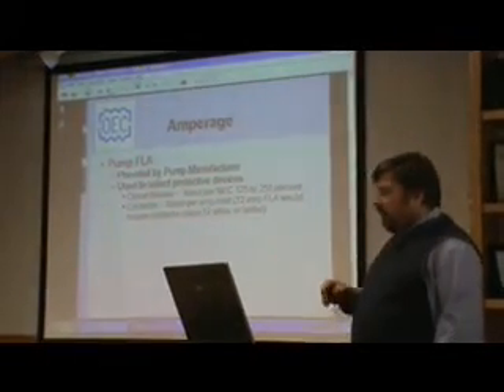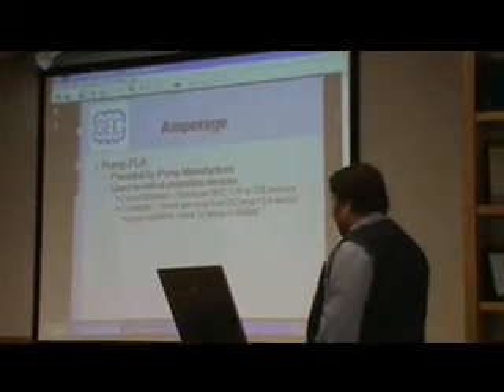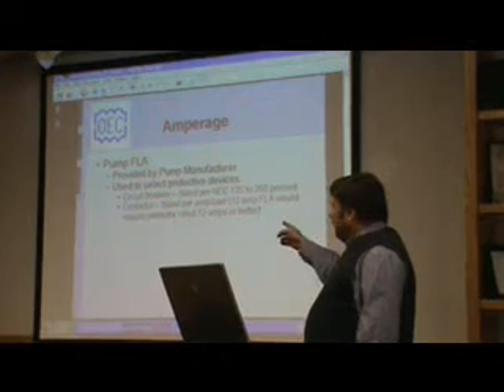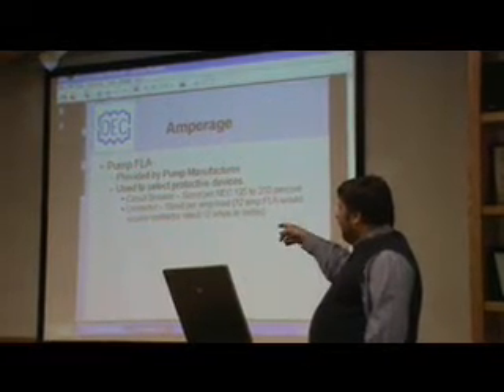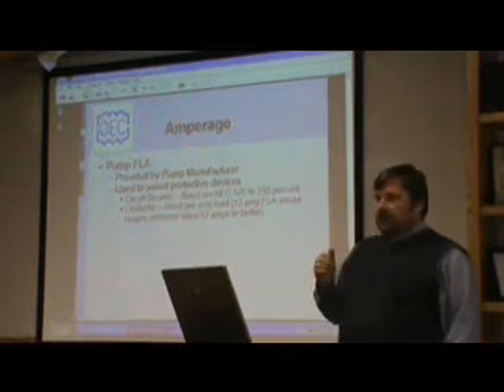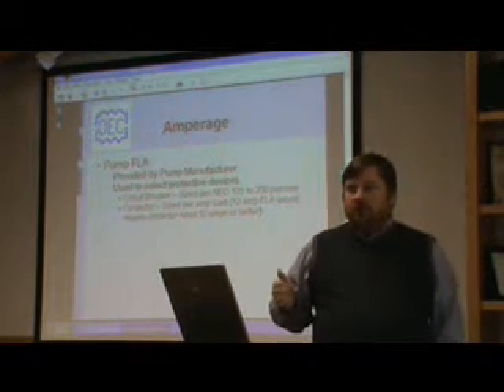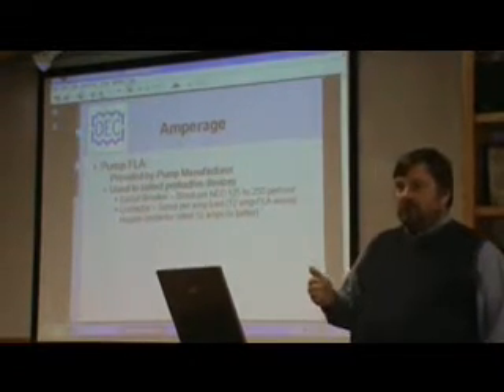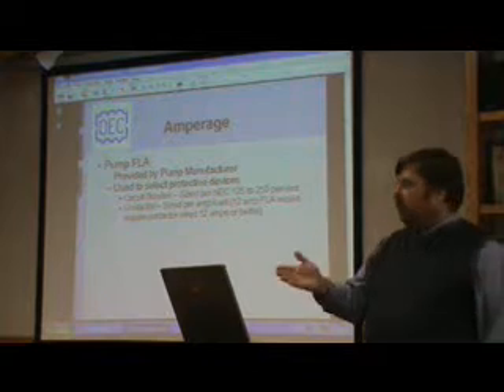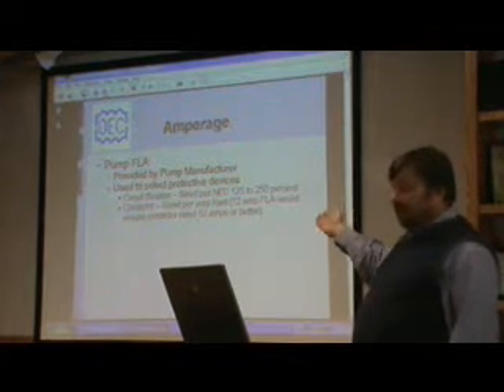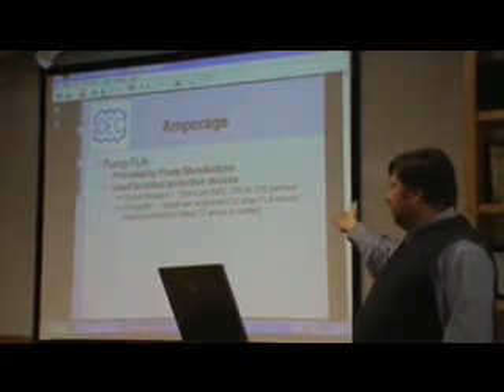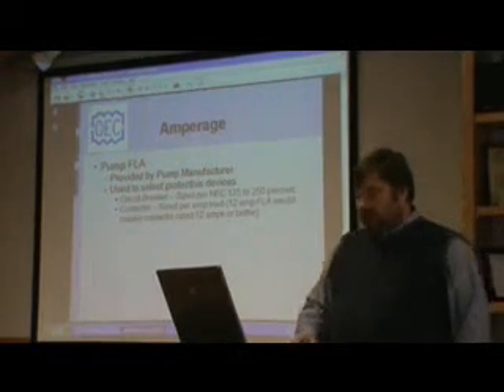And the contactor is sized as a continuous amperage. The IEC contactors, this is an example here of a 12 amp contactor. You want to make sure that that device is sized larger than the amperage that you're going to run the motor for. So if you have a 10 amp pump, you want to make sure that the contactor is rated at least 10, or the first actual value you'll see in IEC is 12 amps.